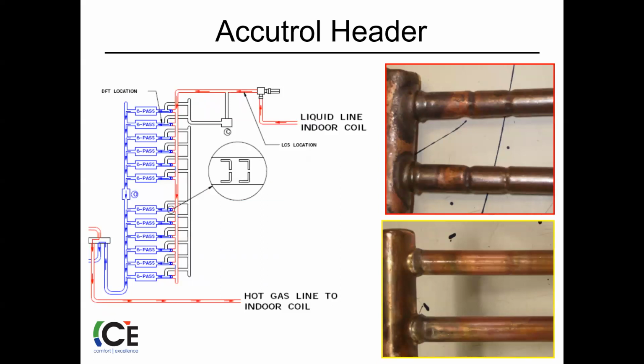So here's the top picture, shows an Accutrol, so it's blown up obviously, but you can see the indents in the piping. That's where the orifice is fixed in position. If your header has smooth pipe, you don't have that type of metering device. So basically it's just, hot gas comes in, it hits that device, and it's distributed evenly through those. If you have a double coil, obviously you're going to have two Accutrols. Otherwise, you're going to have one.